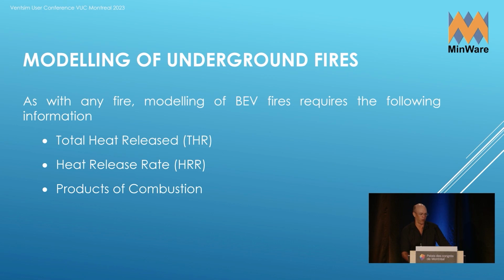When we consider how to model the fire risk of these batteries from a design point of view, we don't treat batteries any differently than other combustibles like tyres or diesel fuel. We've got to consider three things: the total heat released off the battery, the rate of heat release, and the products of combustion. These three things form the risk of your underground fire, and when we consider batteries, those are what we calculate.